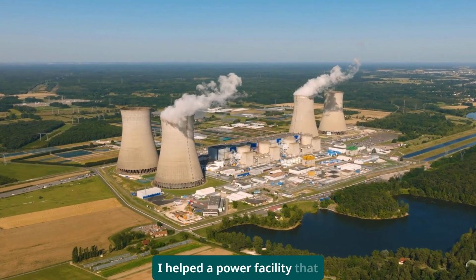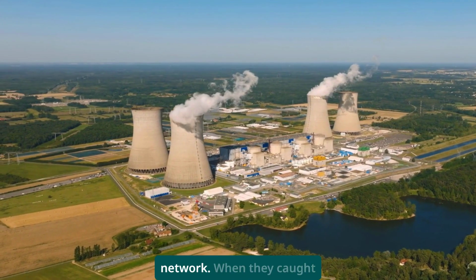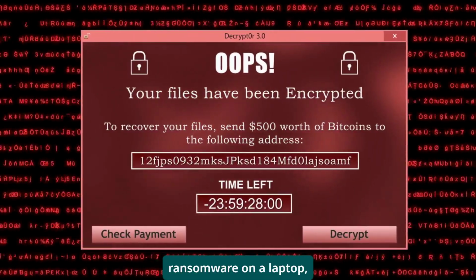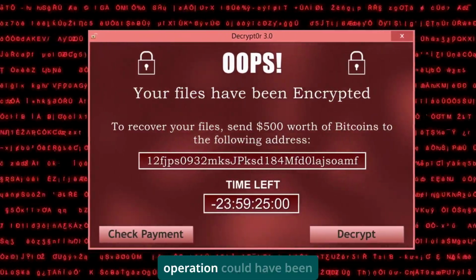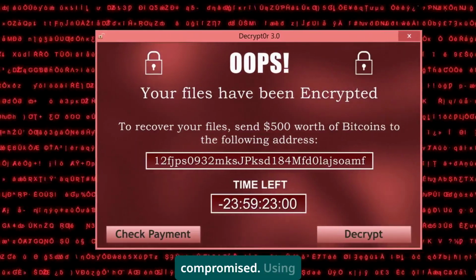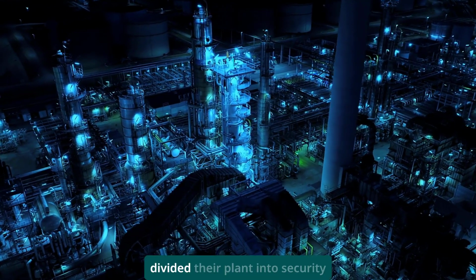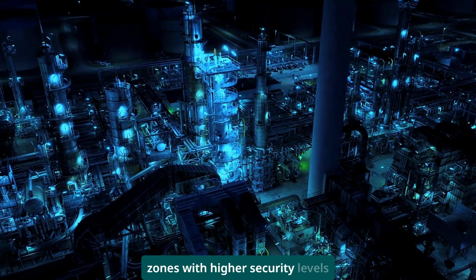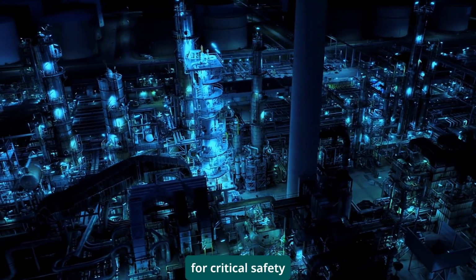I helped a power facility that had everything on one flat network. When they caught ransomware on a laptop, they realized their entire operation could have been compromised. Using 3.2 guidance, we divided their plant into security zones with higher security levels for critical safety systems.